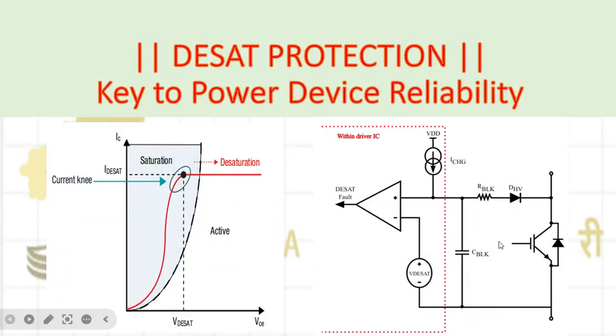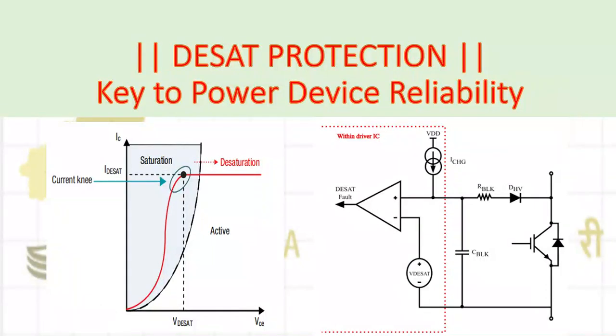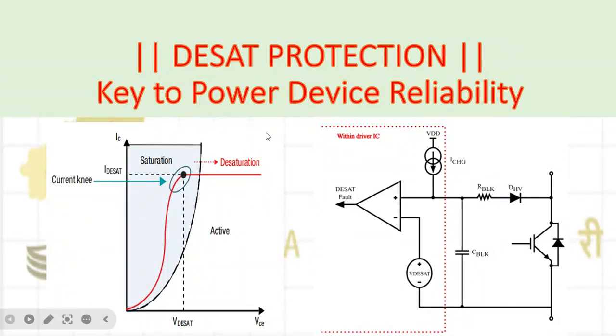On your screen you can see the circuit for DESAT protection: one C_blk, R_blk, and one diode, and a comparator. Using these components we can design a DESAT circuit to protect the device. Now, regarding the name — looking at the IGBT characteristics with saturation, active, and cutoff regions — DESAT means the device is going outside the saturation region, hence the name DESAT.